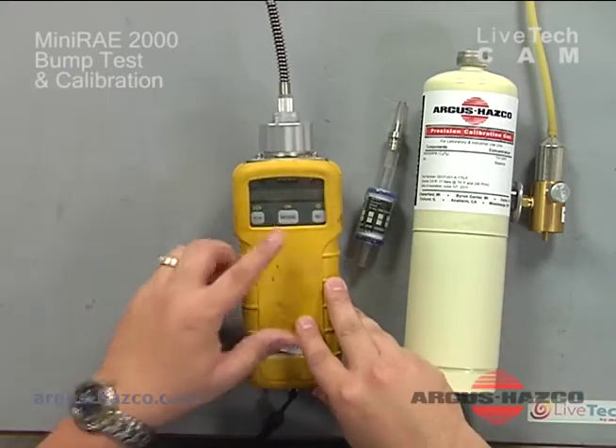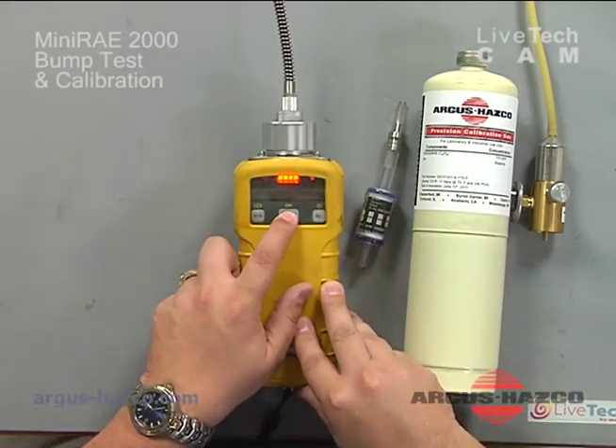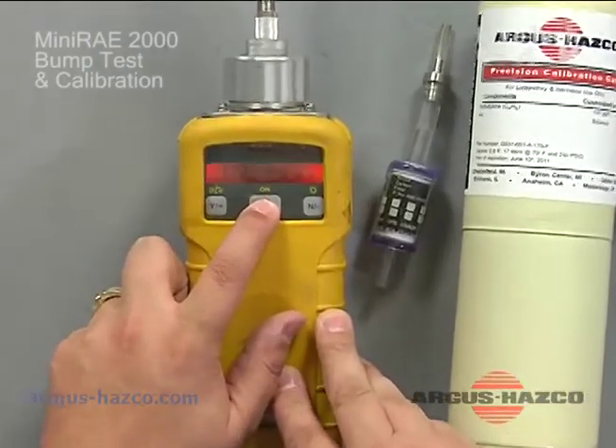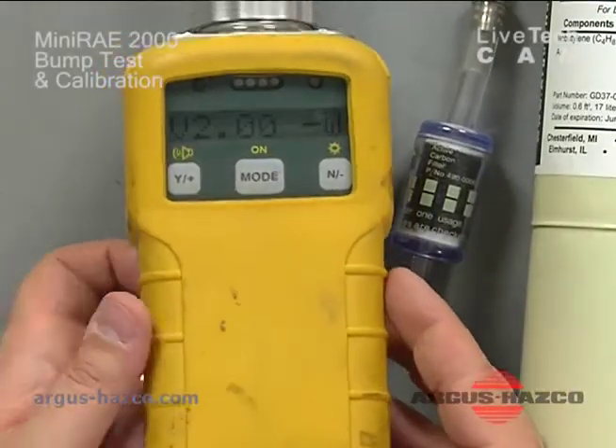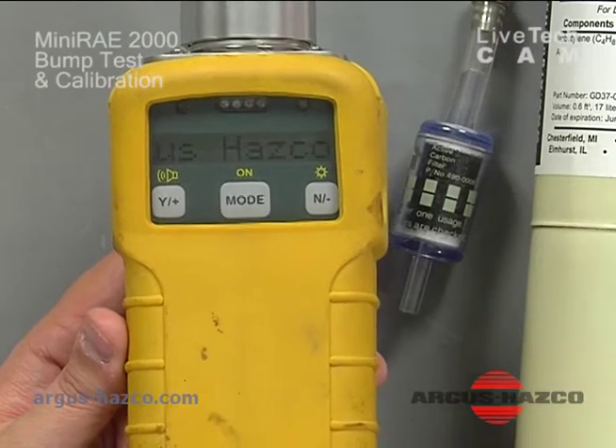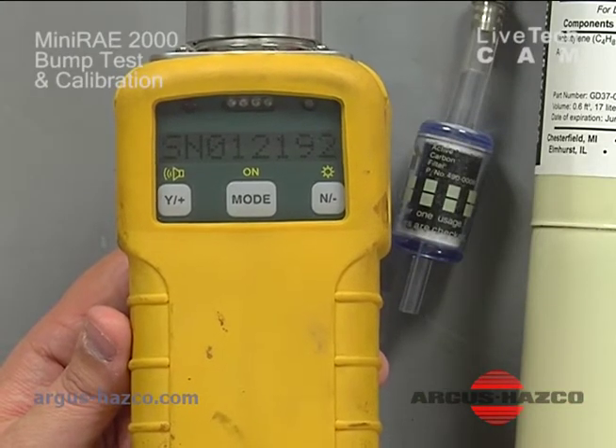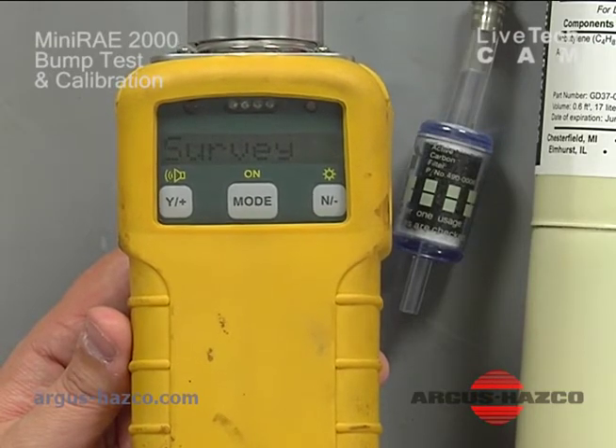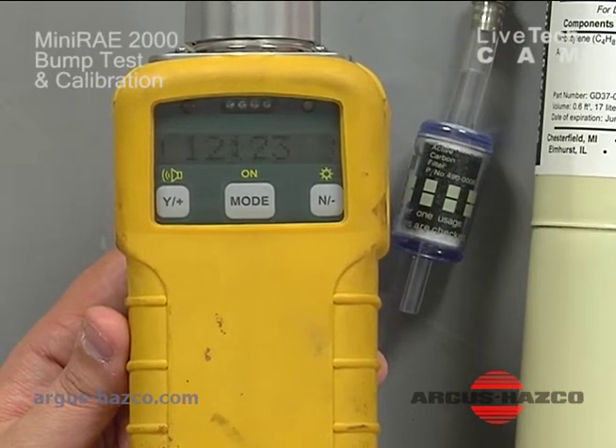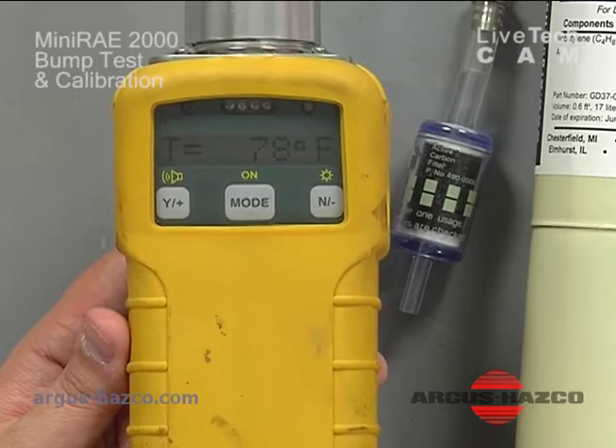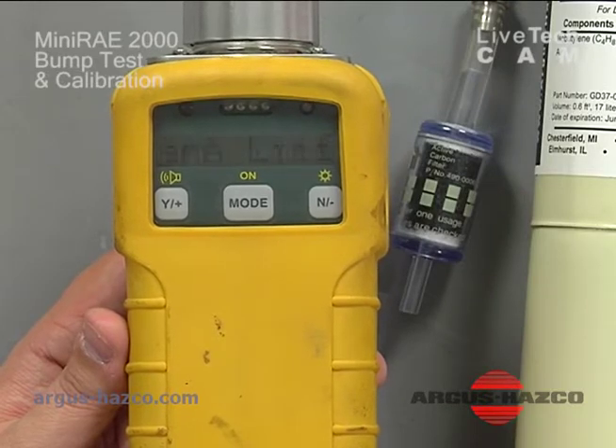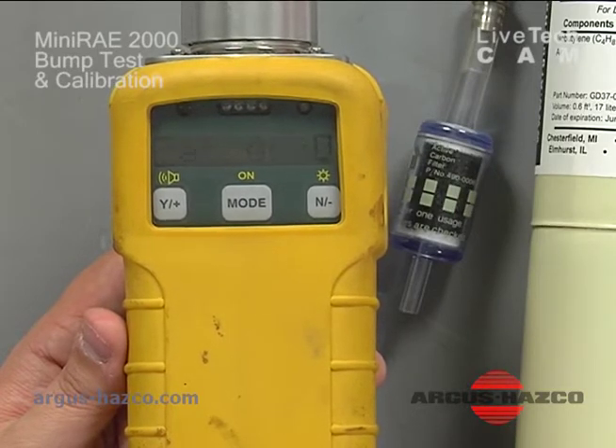So first you will need to turn on your MiniRAE 2000 by pressing and holding the button for a few seconds. When you let go, it'll say on. It'll start going through a warm-up screen. It gives you the serial number of the unit, model. The operation mode is in survey mode, the date, the time, the temperature internally of the instrument. The gas we're using is isobutylene. The alarm limits will indicate that it's set for high of 100 ppm, low of 50. Battery 6.2, it will shut down at 4.2 volts.